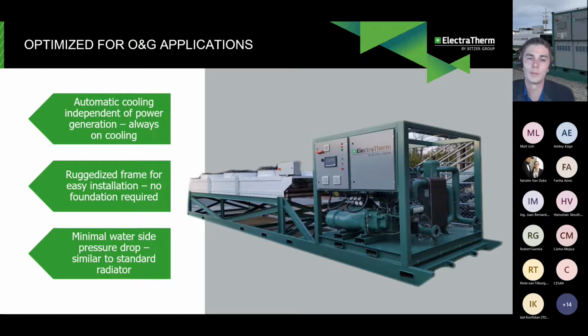Also, as mentioned earlier, I think Matt alluded to it a bit, we're also capable of redundant cooling, but also eliminating derate potentially at sites. So some of those sites out west in the stack shale play experience summertime derate. We have additional cooling capacity compared to a lot of standard coolers because we're cooling our refrigerant to a much lower temperature than that delta or difference that you have in engines. So if engines are going from 190 to 170 degrees, we're dropping our refrigerant down much lower, many times within 20 degrees of ambient conditions. So in that sense, our cooler is actually oversized for the engine because we are cooling it for our power production process.